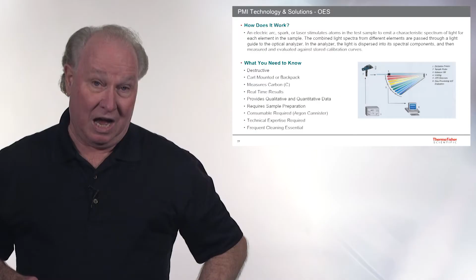The next device I wanted to talk about is the optical device. It's called OES, Optical Emission Spectroscopy. Now this has been out on the market for a long time. It's been used dramatically. And one of the things about that device is that when you sample prep that and you shoot it out, it's an electrical discharge. So inside the handheld portion, you have a probe that sticks out. It's called an electrode. It's sharpened, it's made out of tungsten. Discharges electricity, and that electricity ablates the metal.